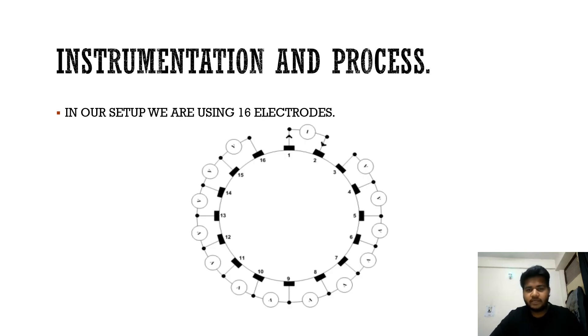Now let us look at the instrumentation and process followed in electrical impedance tomography. In the setup we are using, 16 electrodes are arranged as shown here. We inject current between any two electrodes and measure the voltage between all other pairs of electrodes. This process is repeated for all possible pairs of electrodes.